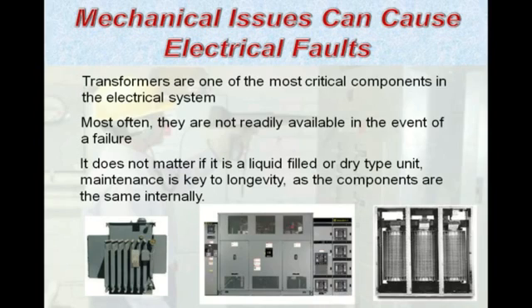It's not going to matter if we are discussing a liquid-filled unit or a dry-type unit. The reality is maintenance is key to longevity, as we know, and the components within these units are essentially the same. So the same principle of operation, the same maintenance considerations, the same failure points.